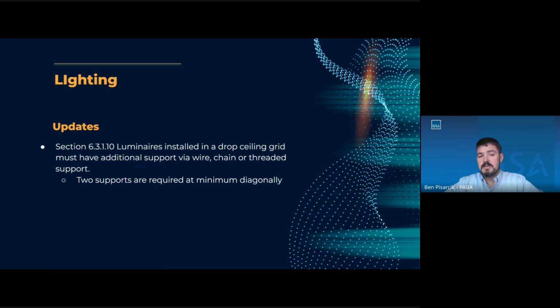I'm sure we've all seen in the field. Yeah, and that's specifically for power over Ethernet. So, yeah. Another question, has there been a notification or communication with the Building Technology Services Division, IT, to coordinate IP addressable lighting control, scanning, and remediation? Yes, that's a great question, and there would be if it was specified on a project. We definitely have them get involved. And if I'm not mistaken, one of those previous bullets mentioned IT owning the switches. Yes, and that is in the P100 as such that way too.